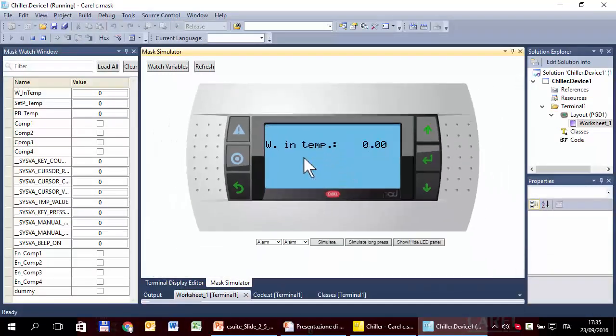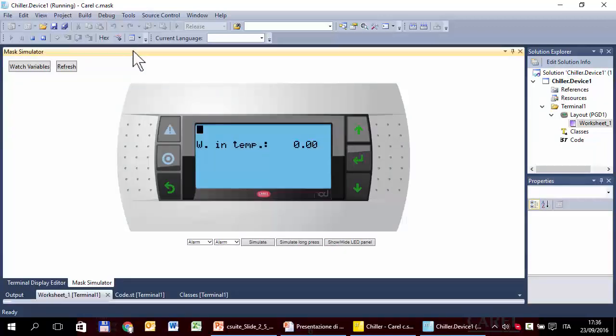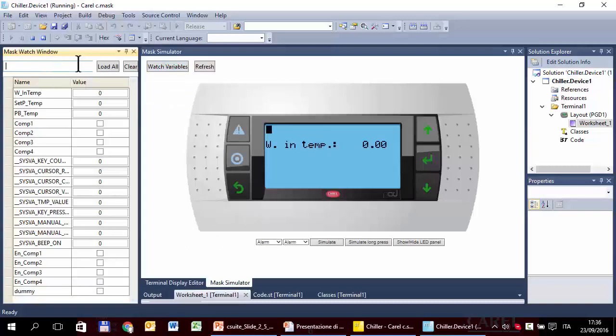Zoom out. If you don't see the variable here, or even worse if you don't see this list, you can click Variable > Watch Variables, then load all current variables. We can see that Enable Compressor One, Two, Three, Four are all off. We need to set them to one just to check if the compressors start.